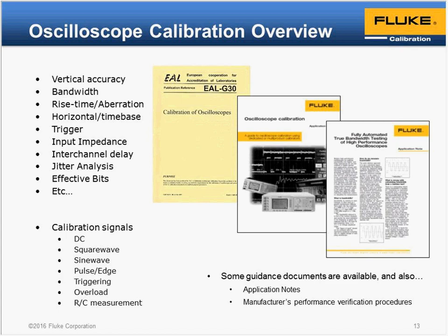Clearly, there is any recommendation that the manufacturer may put into their published literature, their handbooks, calibration verification, performance test procedures for the oscilloscope. A good reference is any specifications and characteristics contained in the specifications and datasheet for the scope. Plus, there are some other guidance documents around. I've got a picture on that slide there of an EA guide. That's rather an old picture, unfortunately. That document has recently gone through a revision and re-release. I believe it's also available as a PDF.